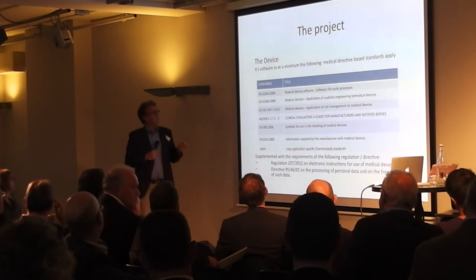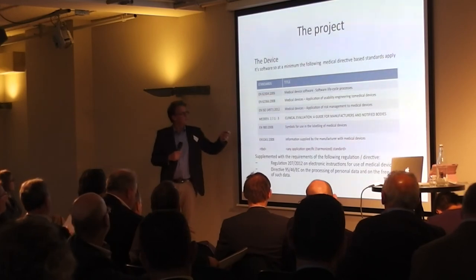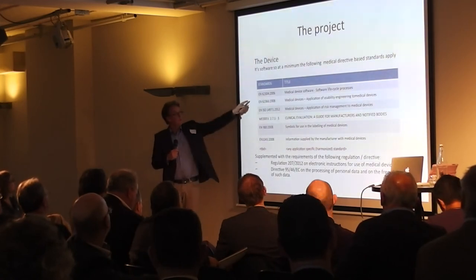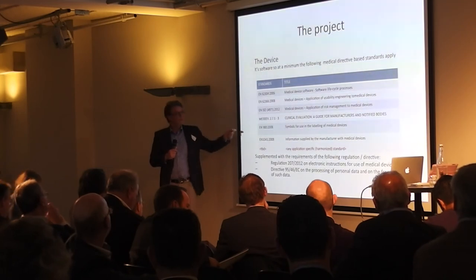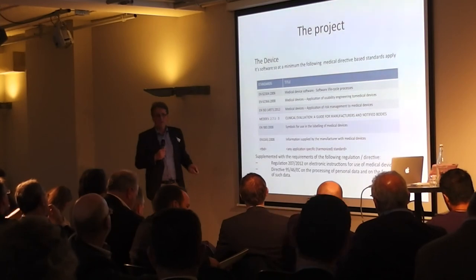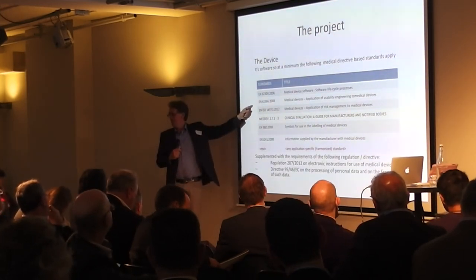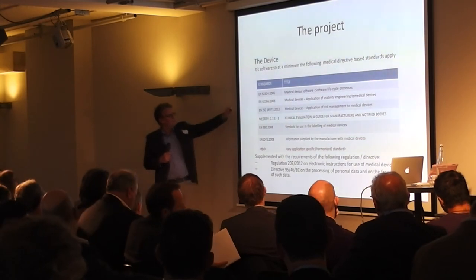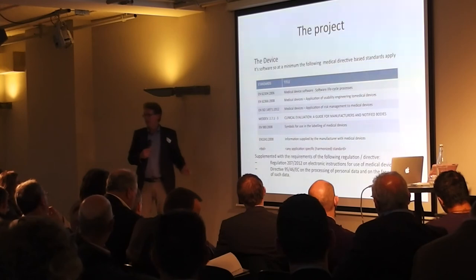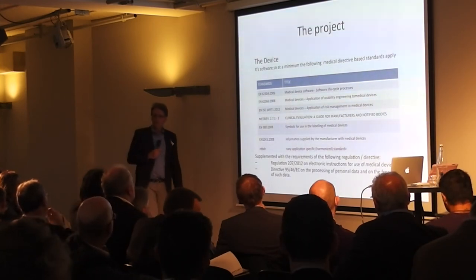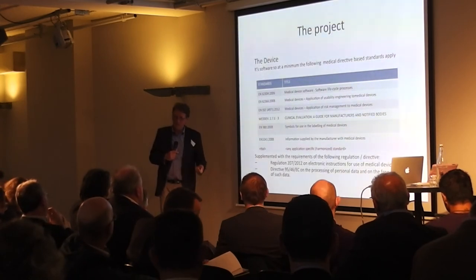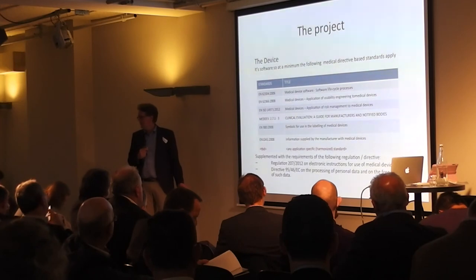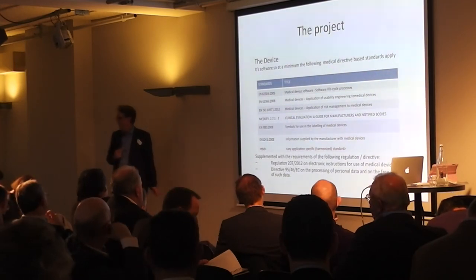An app is software, so as a minimum a number of software standards apply. This is IEC 62304 — medical device software lifecycle. This covers software requirements throughout the whole lifecycle, structured like a V-model for software development. And the app and user interface require usability standards to be applied. These are the core software entities. Important and driving through all of this is the risk management process — what are the risks to the product, what mitigation methods do you need to implement, and are they correctly implemented? This is also the quality system dimension.